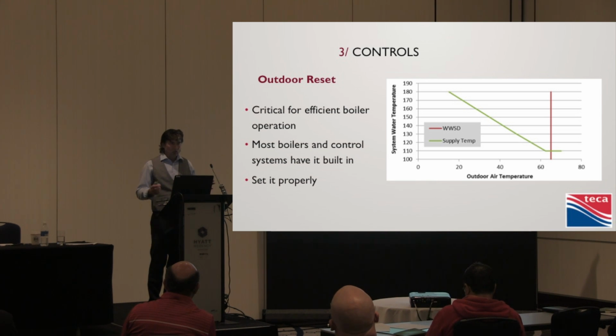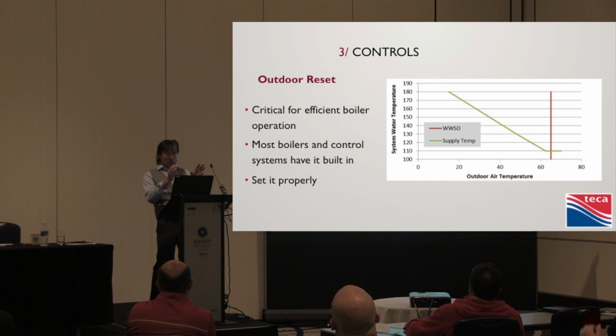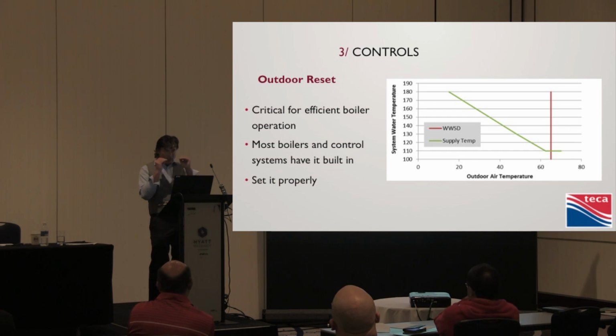Dial it in. So between load matching of your burner to heat to the temperature, tell it what temperature to heat to. Make sure it's as cool as possible. This is how you do it with these controls built into virtually every boiler I know of now, including that goofy electric boiler.